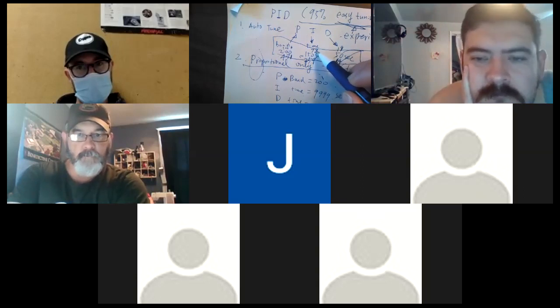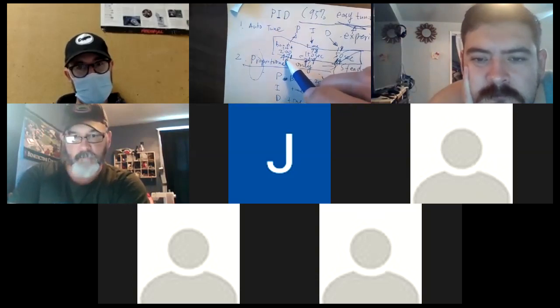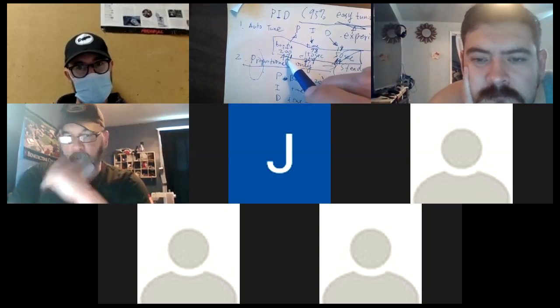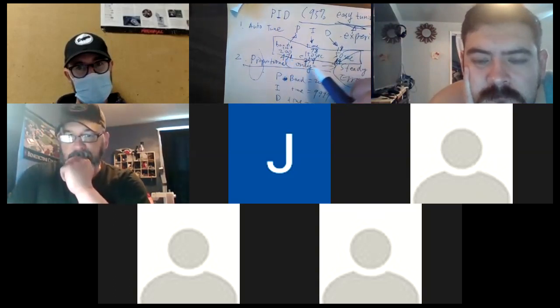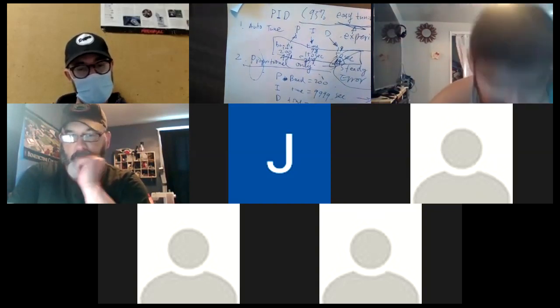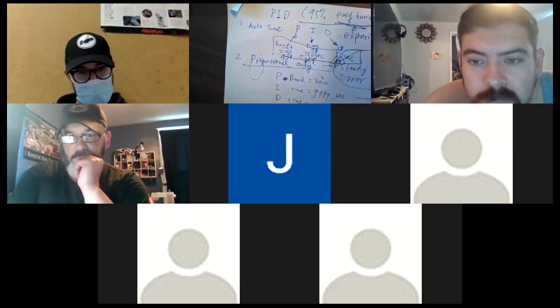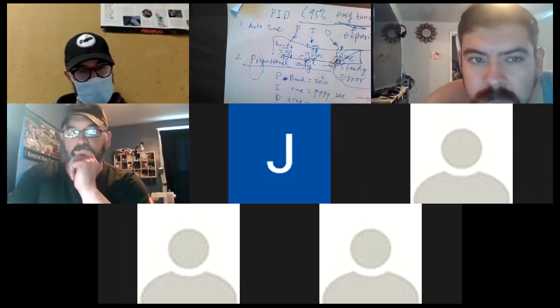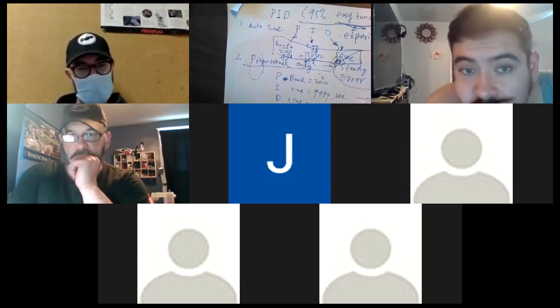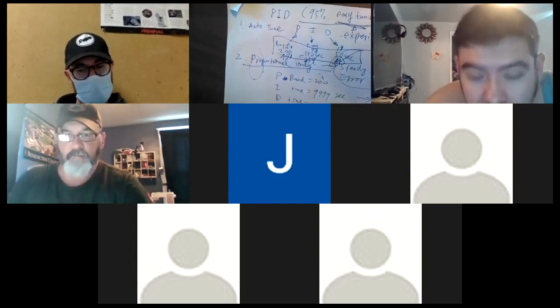So Tim has a very small derivative and a very high integral. I have a very high integral and high proportional compared with mine. Joe has a small proportional because the band is almost 500. That means the gain is very low. Very small integral also. And a big derivative, because your controller is so powerful. The derivative means braking and boost. When your controller is controlling too fast, the derivative will brake your controller. It's just like parking your boat. When you are far away from your target, you accelerate your boat. When you almost reach your target, you brake your boat.